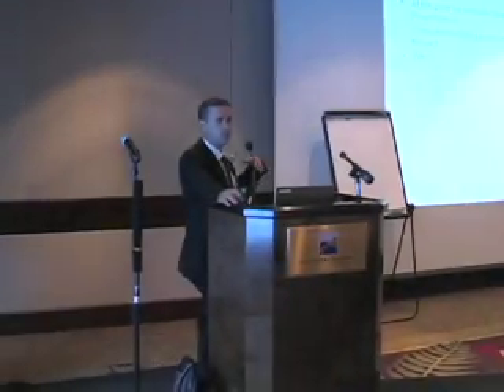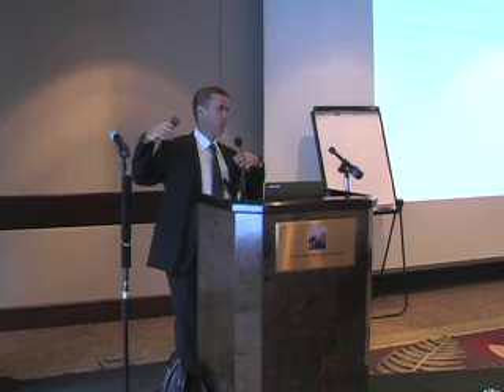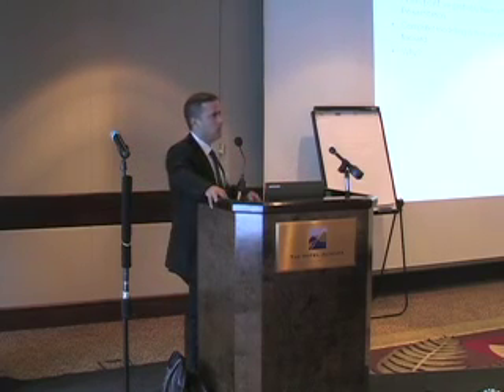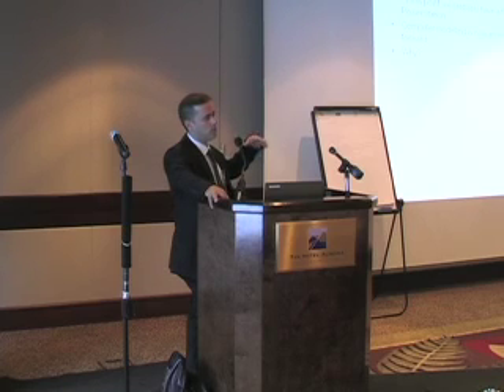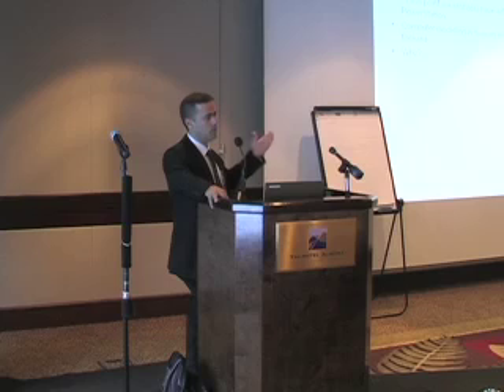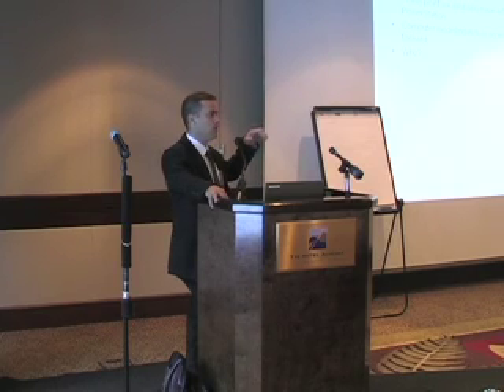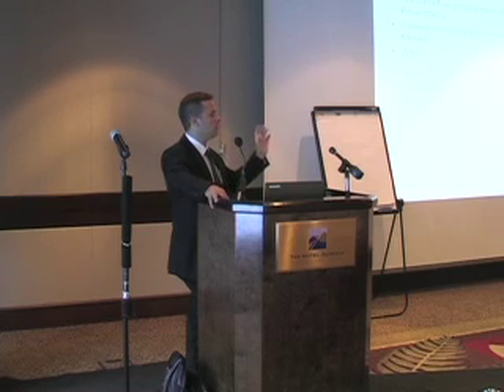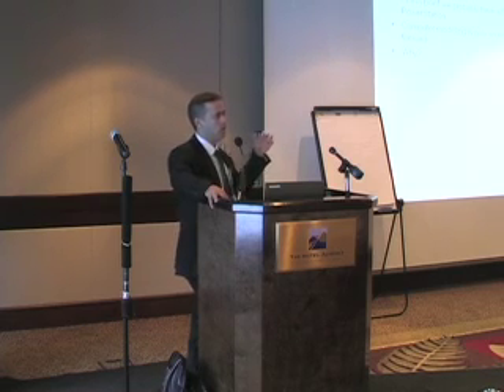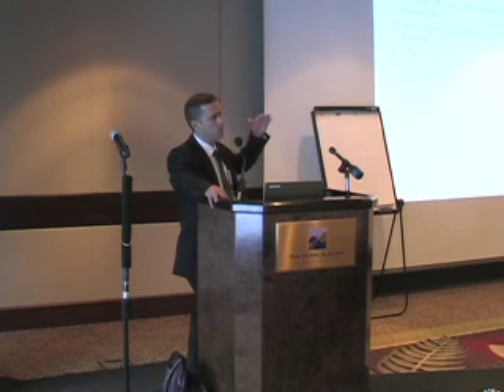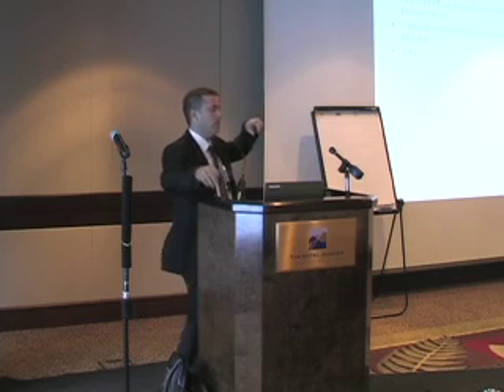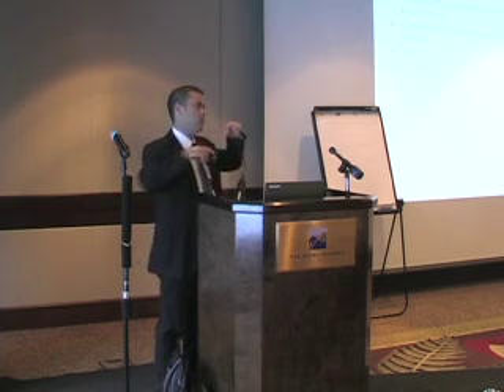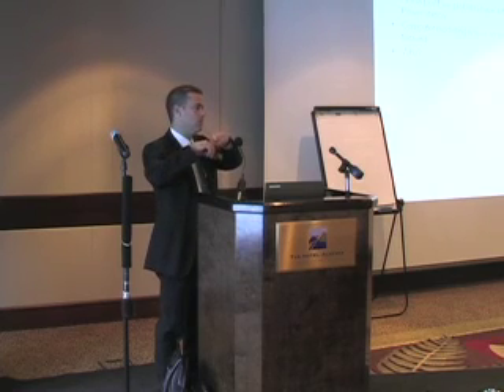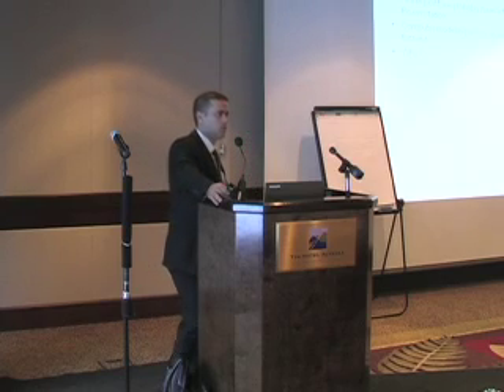It was a high voltage transmission line, 11 kV, 11,000 volts, and we went back to the protection engineers and said, surely once we got 3 or 4 generators running, we had enough inertia to trip the protection you had. And they said, well, interestingly enough, there wasn't that much monitoring equipment on site, so no one really knew why it didn't trip. There was no high-speed graphs trending this, but it seemed that the trip protection relays they have there are quite basic, and the voltage would dip and then raise and dip and raise as the cable was chewing out the steel, touching the steel, not touching the steel every couple of seconds, and it wasn't long enough for the protection relays to ever trip.